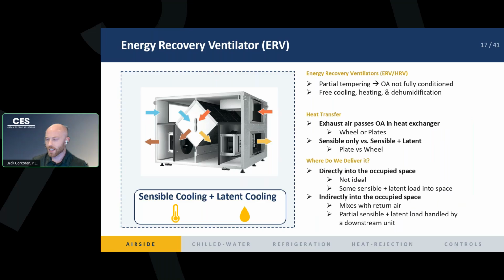And just like our outside air fan, we can dump it directly into the space, right? Maybe our space does not need... We wanted to get rid of 95-degree hot, humid air. We land somewhere in the 81 degrees air. Maybe that's more acceptable to be dumped directly into the space, right? More often than not, ERVs dump into a mixing box and then go into a downstream coil, right? And all that does, as we said, is lower the capacity required of your downstream coil, right? You don't have to do as much of a lift because you got some free cooling and heating and dehumidification with the ERV.